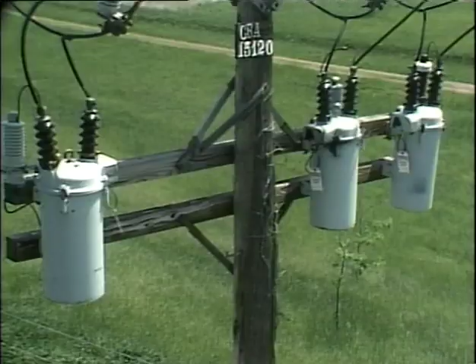Let's start by seeing how a de-energized circuit can become energized accidentally. To de-energize this circuit, a switch was opened and tagged out. If the switch is tagged incorrectly or not tagged at all, it could be closed by personnel not aware of work being done on the circuit. This could cause the lines to suddenly become energized if the circuit hasn't been isolated and grounded.